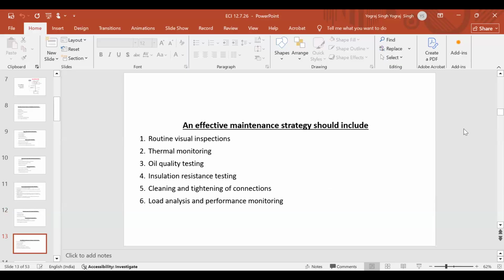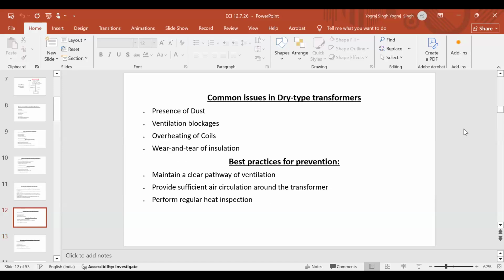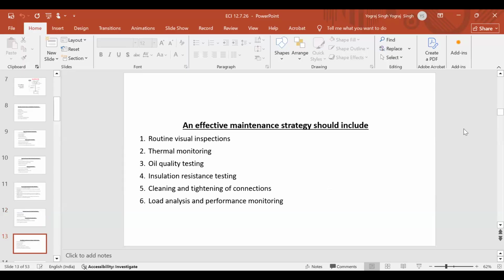Now, overall, if I come to the transformer, what is my effective strategy? Routine visual inspections, thermal monitoring, oil quality testing. In the case of an oil filled transformer, what should be the oil rating? 50 kV per centimeter. This is what IS says. Insulation resistance testing, cleaning and tightening of connections. So these things are known.